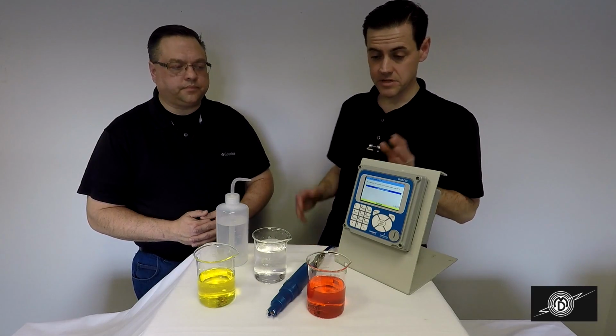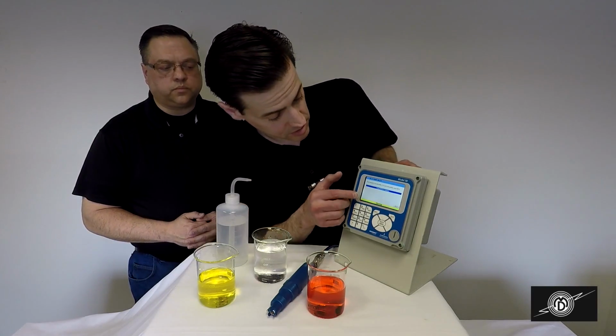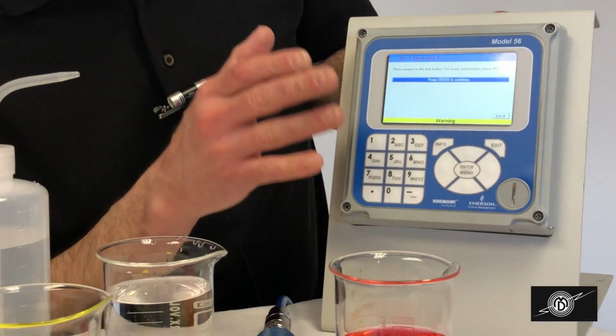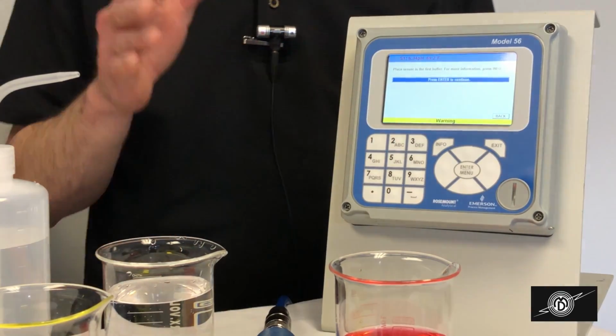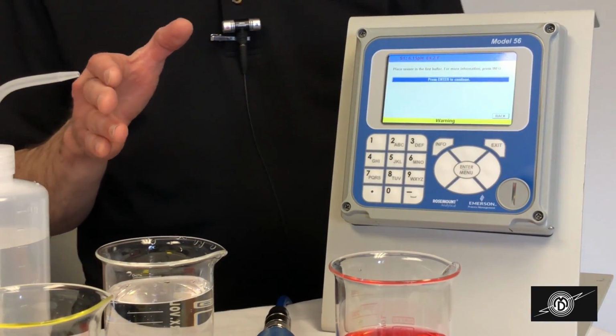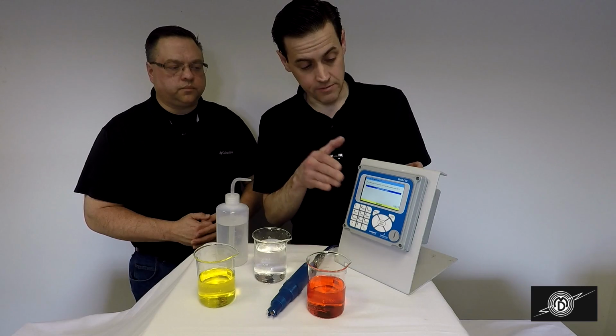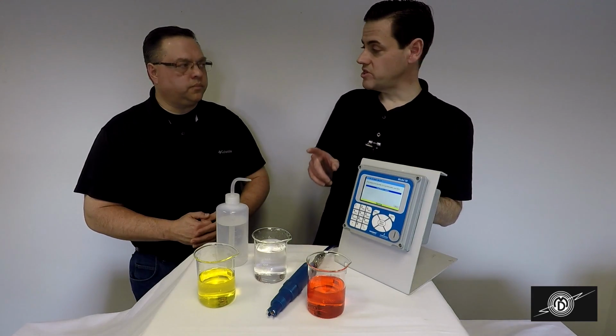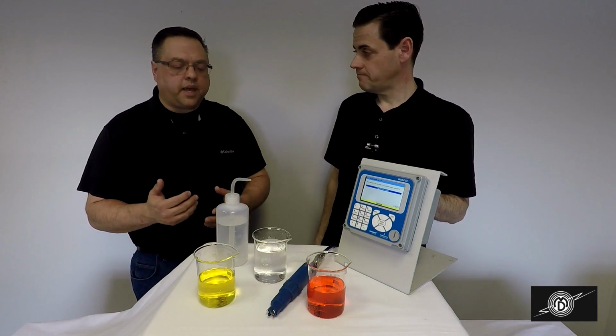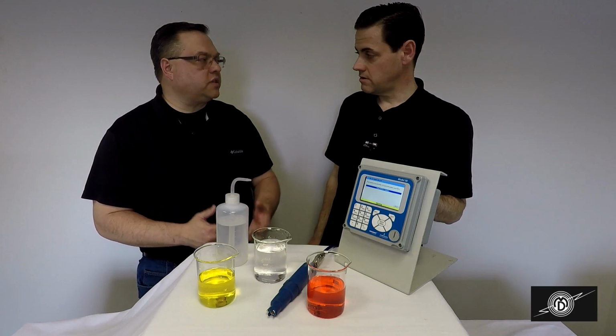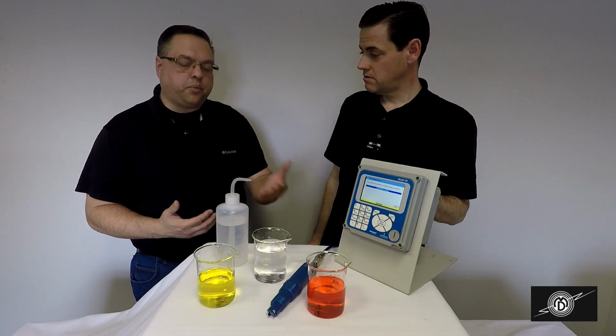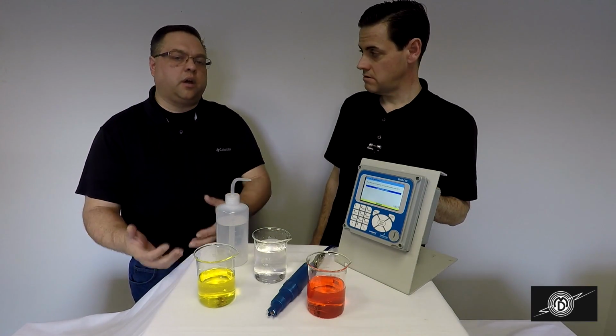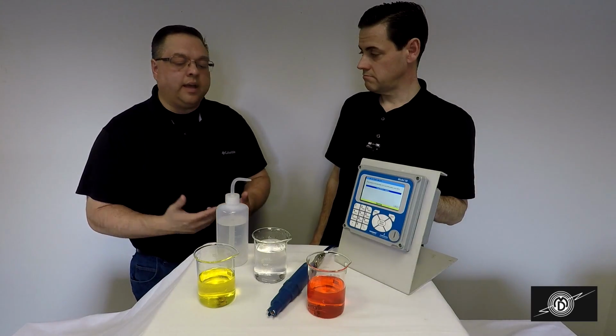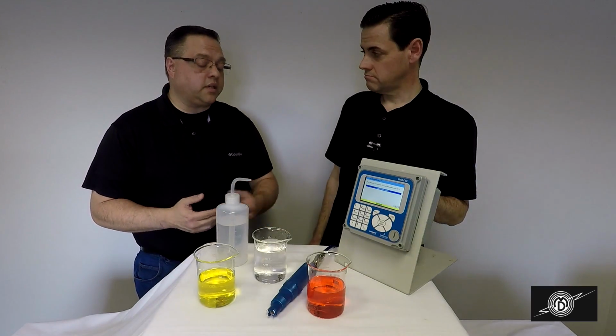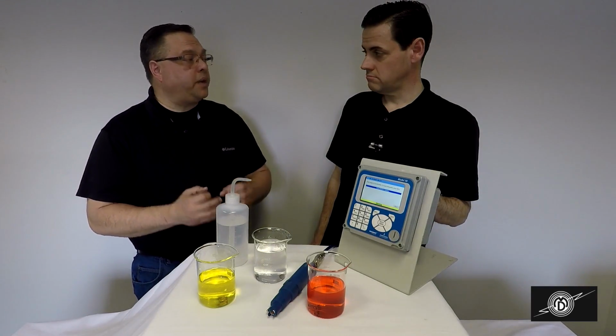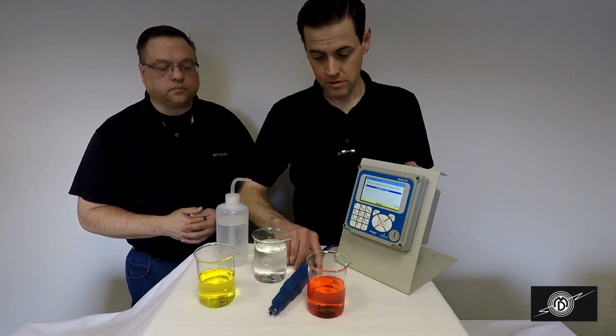Okay. Well, that being said, we're all ready to do the calibration. So what it says here is place the sensor in the first buffer. In this case, it's going to be the 7 buffer, and then we can adjust the instrument from there. Now, why do we start with a 7 buffer? Again, pH sensors see a millivolt signal. When the probe is placed in the buffer solution, a millivolt signal is generated. 7 buffer to a pH sensor is 0 millivolts. It's your baseline. Okay. So we're going to do that.